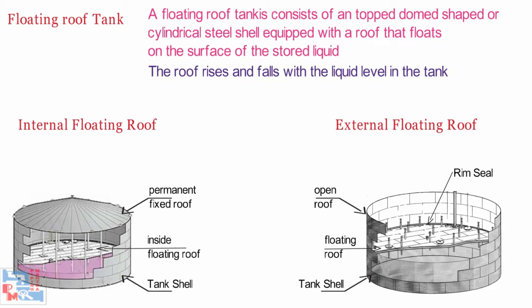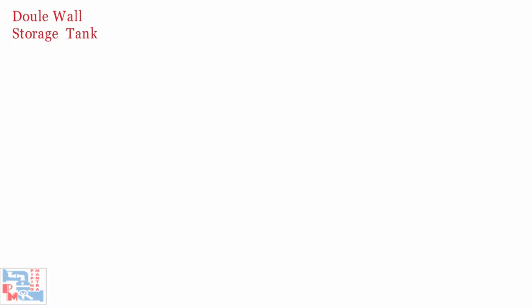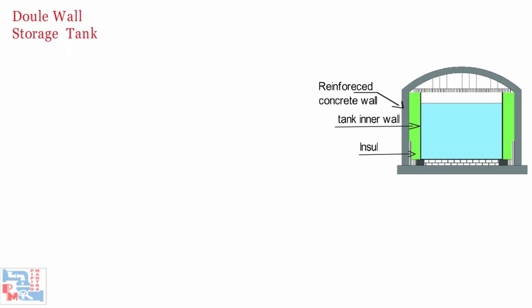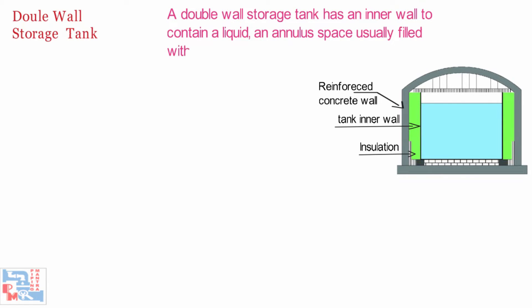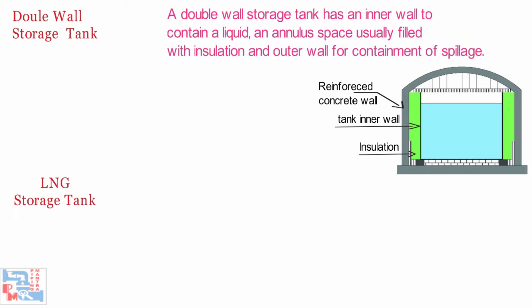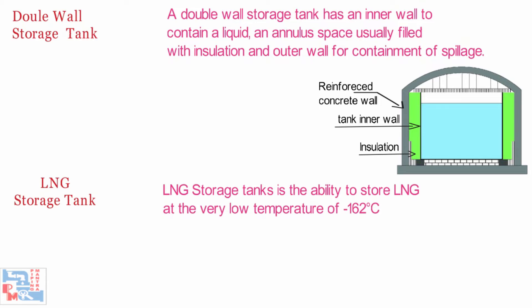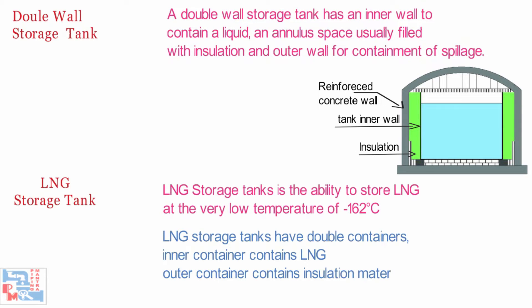The floating deck is also equipped with fittings that penetrate the deck and serve operational functions. Next is the Double Wall Storage Tank — it has an inner wall to contain a liquid, an annular space usually filled with insulation, and an outer wall for containment of spillage. The last one is the LNG Storage Tank — a specialized type used for the storage of liquefied natural gas. LNG storage tanks can be found in-ground, above ground, or in LNG carriers. They store LNG at the very low temperature of minus 162 degrees Celsius and have double containers, where the inner container holds LNG and the outer container contains insulation material.